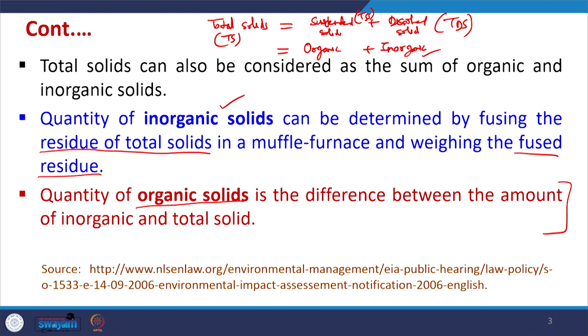Depending on the amount of total organic solid present per litre of the sample, we can know beforehand whether we should go for biological treatment of wastewater. If the inorganic content is very high, we have to rely more on physicochemical treatment, and we can also tentatively determine the amount of sludge that will be produced from physicochemical treatment.